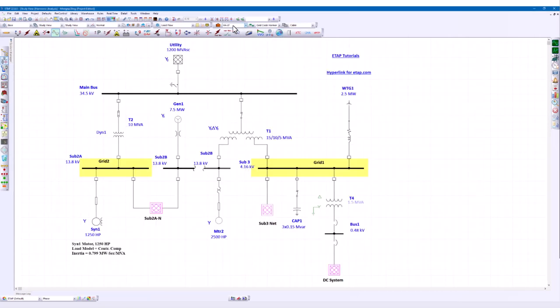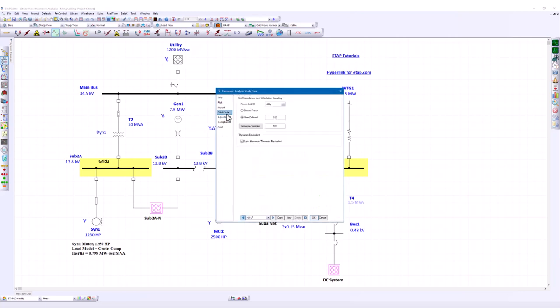The next step is to set up the harmonic study case. Let's go to the grid code page. Firstly, you need to select the power grid ID, and then we are going to generate the sample points. A typical number of sample points required by the TSO is 2,000 to 3,000. When we run the calculations, you don't have to always run 3,000 points every time. As mentioned earlier, this will take thousands of calculations at the backstage, which would take relatively longer time as your sample points increase. In many cases, if you are just going to run a quick evaluation before the very final stage, you have the option to user define a smaller number for the calculation in order to save some time. And you also have the option to choose corner points only to have a very simplified and fast evaluation.